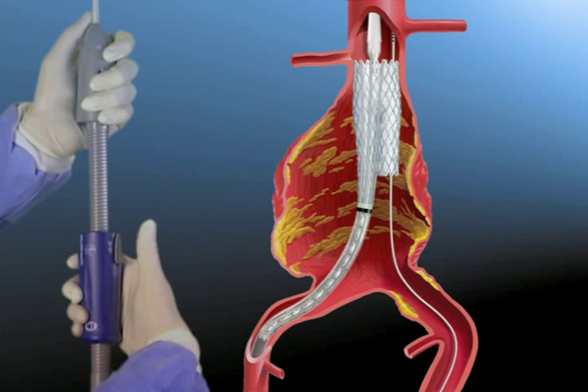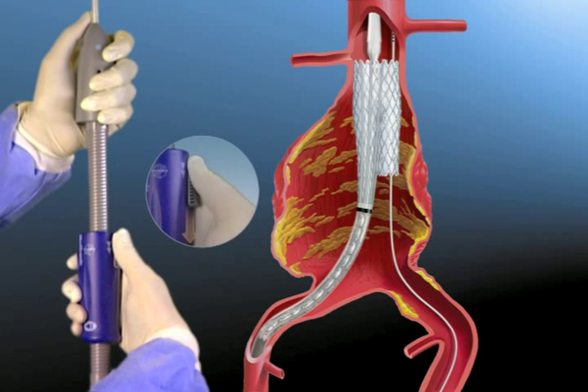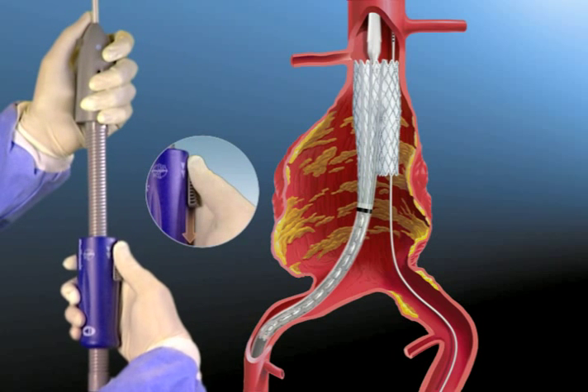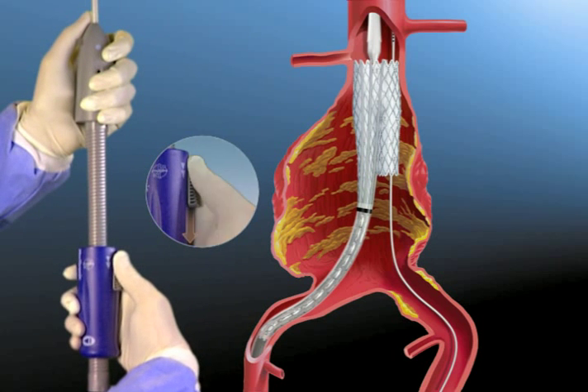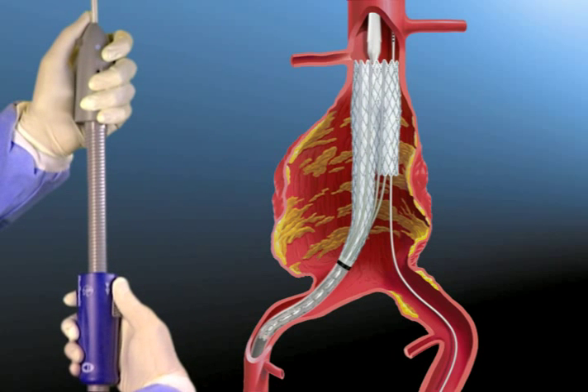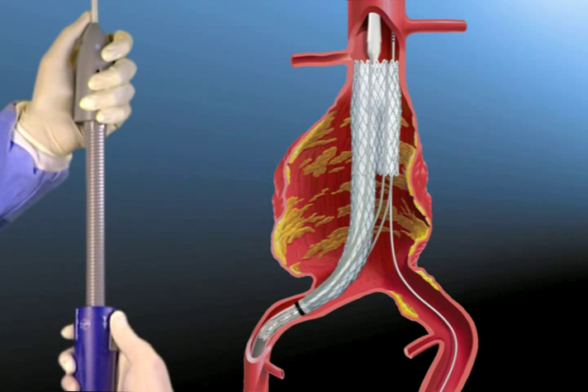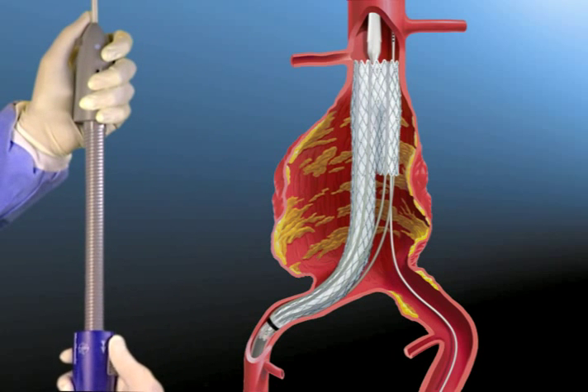To deploy the distal end of the stent graft, hold the delivery system stationary and retract the graft cover until it is just below the distal radiopaque marker on the delivery catheter.